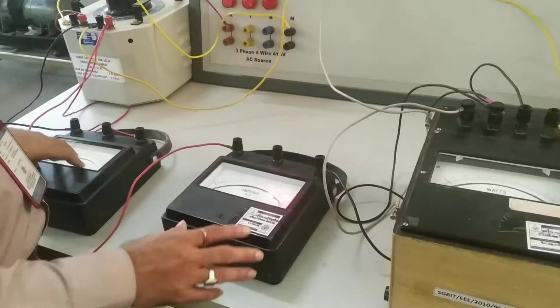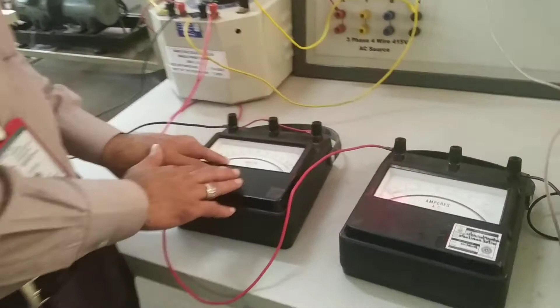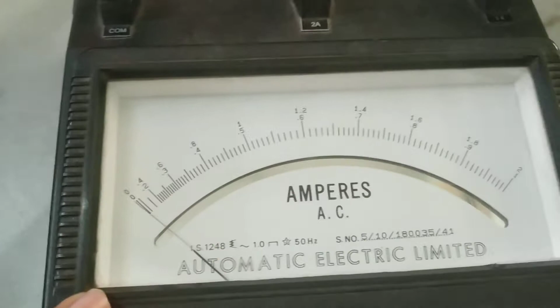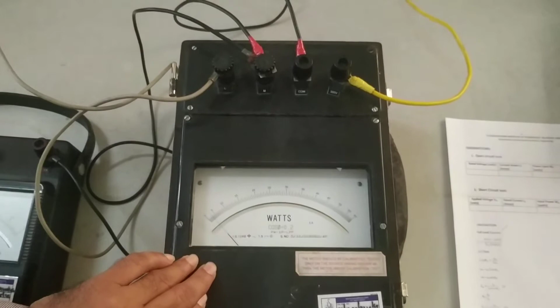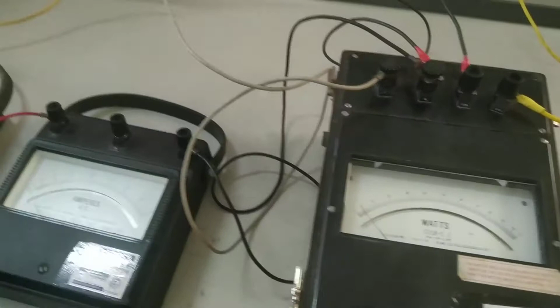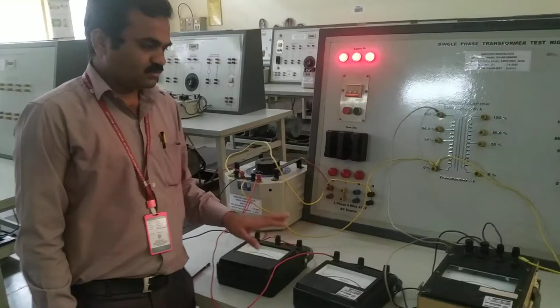With the help of the circuit diagram we can make it. We need one voltmeter to get the voltage reading during the OC test, one ammeter to get the current reading, and one wattmeter, the LPF wattmeter, to get the power consumed during the open circuit test. These are the components used to conduct the OC as well as the SC test. First we need to see how the OC test can be conducted on a single phase transformer.